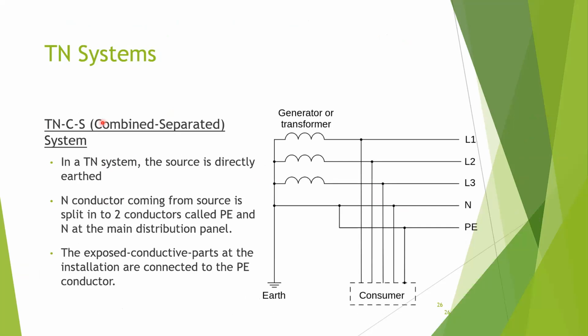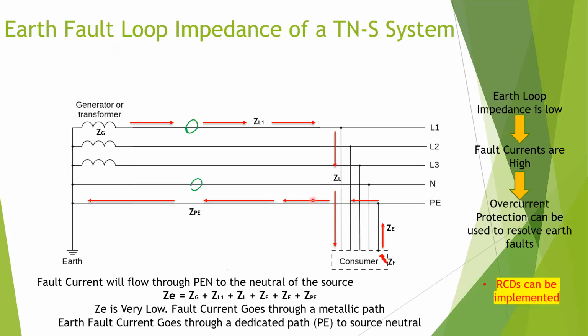And now we have the TNCS. TN, that means we have combined and separated. That means you do not have a separate PE conductor coming out of the source. We have a shorter PE conductor which is connected to neutral. Earlier, this conductor was going to the source and again connecting to the neutral. But what we are doing in the TNCS system is taking the PE conductor from somewhere around here, usually from the main distribution panel. So usually TNCS systems are installed in Sri Lanka.